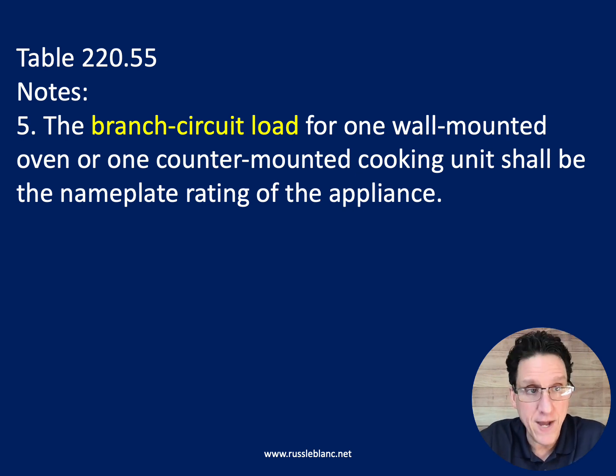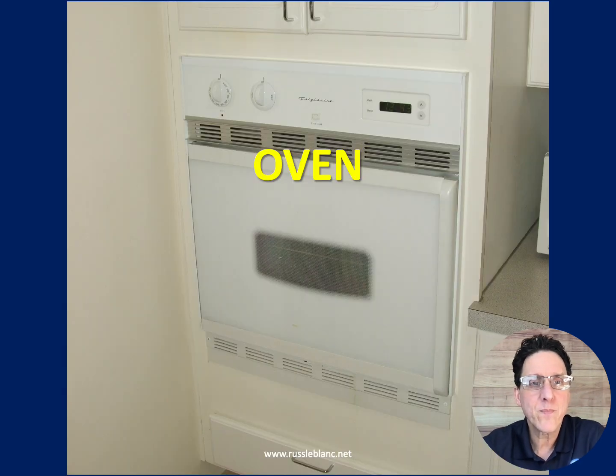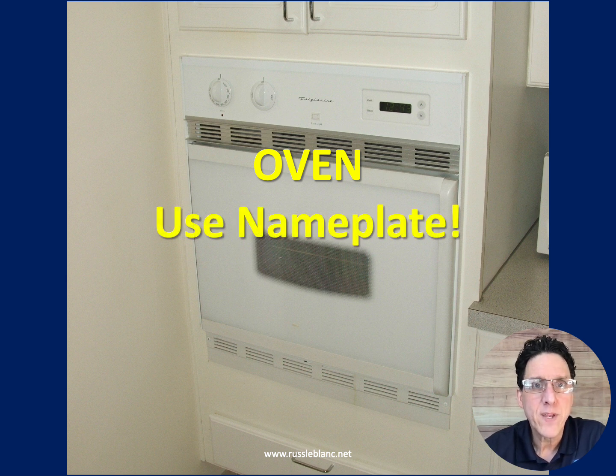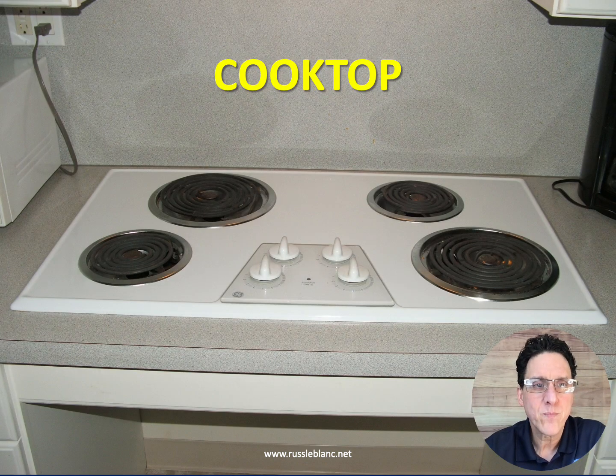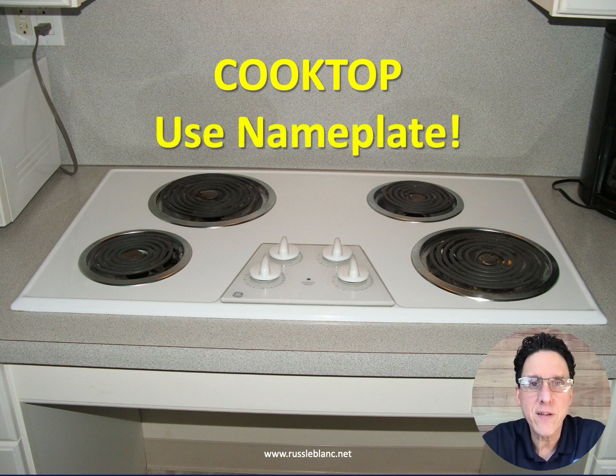But then we have note 5, and that says the branch circuit load for one wall-mounted oven or one counter-mounted cooking unit shall be the nameplate rating of the appliance, right? So we have to understand what's a range, what's an oven, and what's a cooktop. All right, so that is an oven on the screen there, right? And note 5 says use the nameplate. Do not use table 220.55. Use the nameplate instead. And then we have a cooktop. You've got to use the nameplate to calculate the branch circuit load for a cooktop as well.